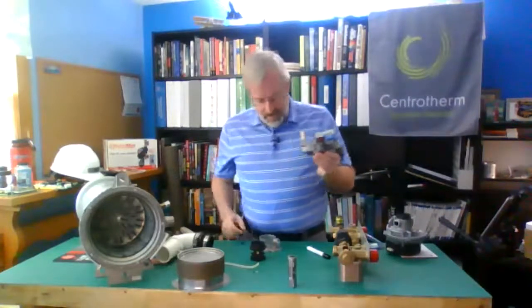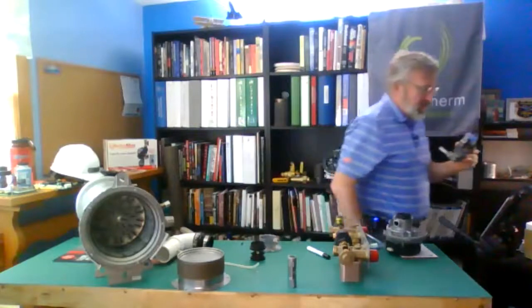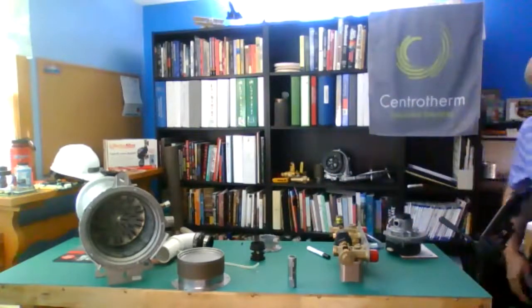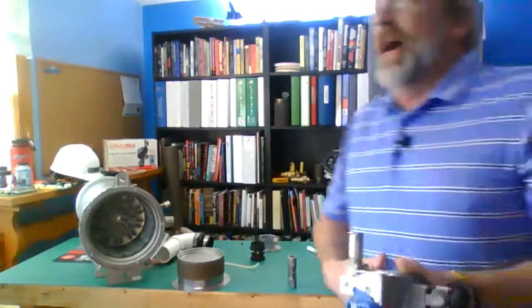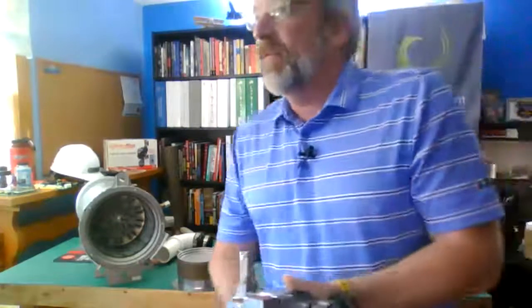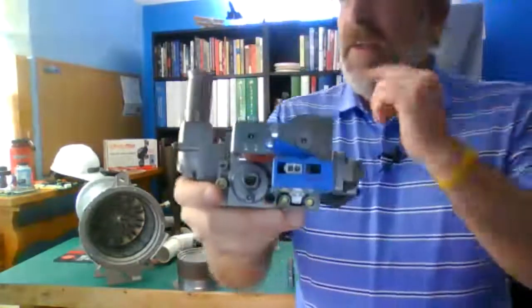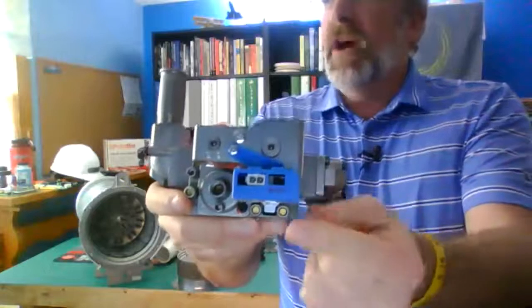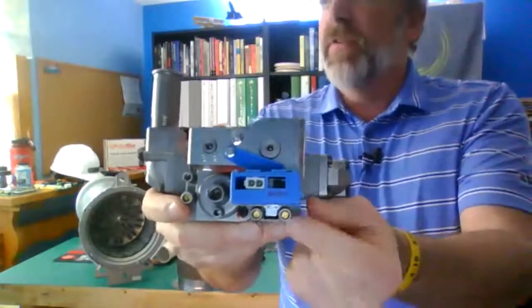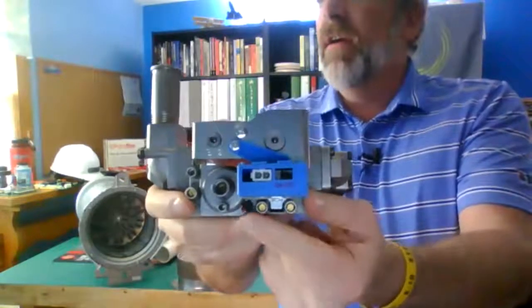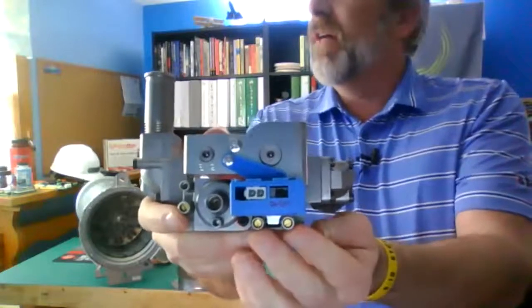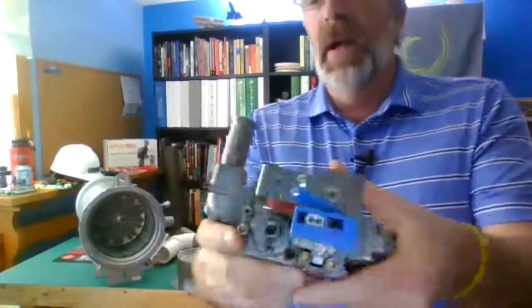So that's that combustion. Now, what I didn't talk about is how do I adjust combustion? The gas valve has two adjustments on it. I'm actually going to move around here, get you guys a little better view. We talked about those pressure test ports. Positive pressure here, negative pressure here. Okay, that's where I'm putting my manometer on.